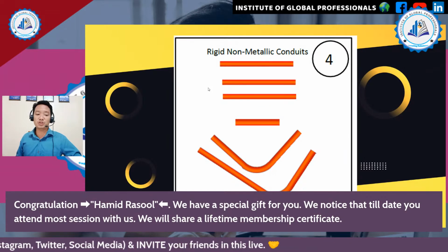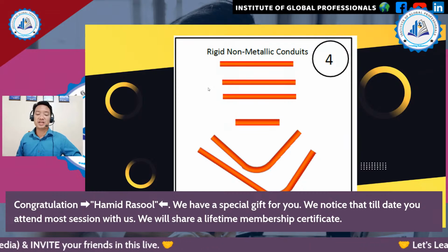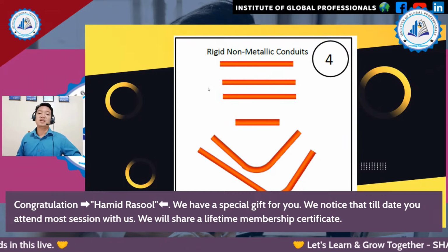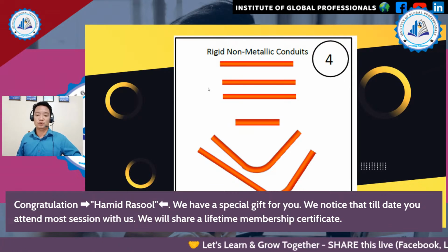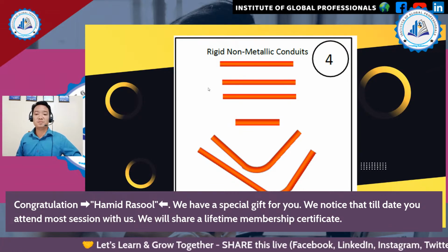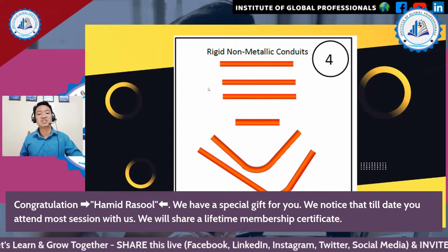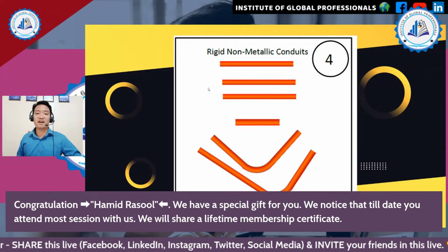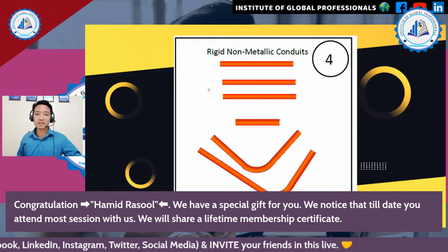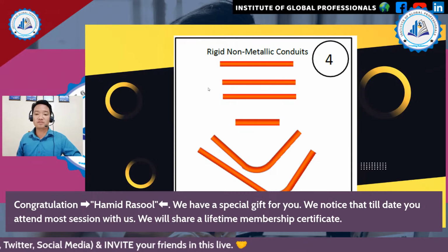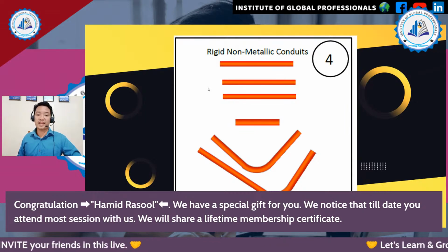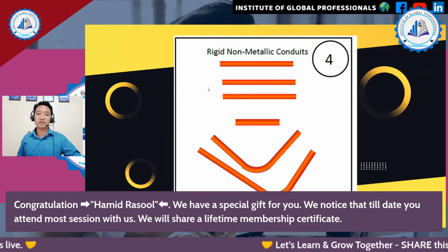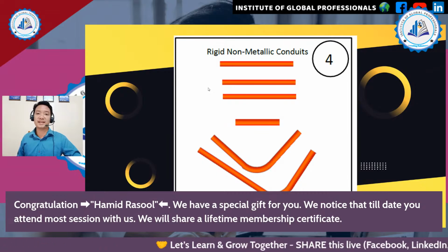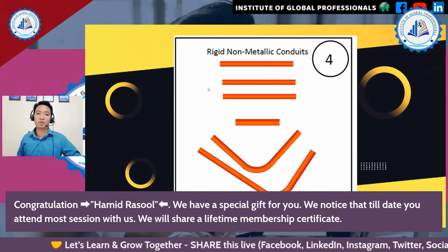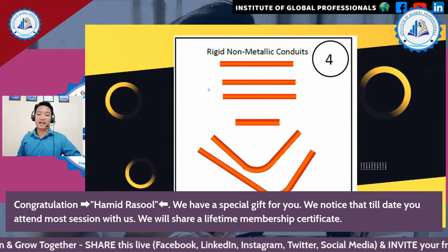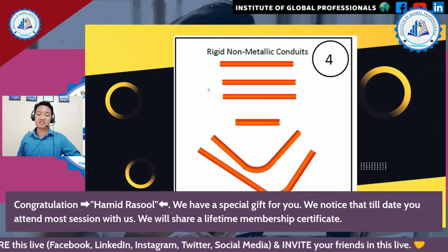And the job required you to have a rigid experience for you to bend a simple type of metallic or non-metallic conduit. So this time, we'll be using the PVC or the rigid non-metallic conduit. It varies in sizes, wherein we'll be using 1/2 inch of the non-metallic conduit, and it should always be in orange color because it is used in electrical installation. For water, we use color blue, and for metal, we use the silver.